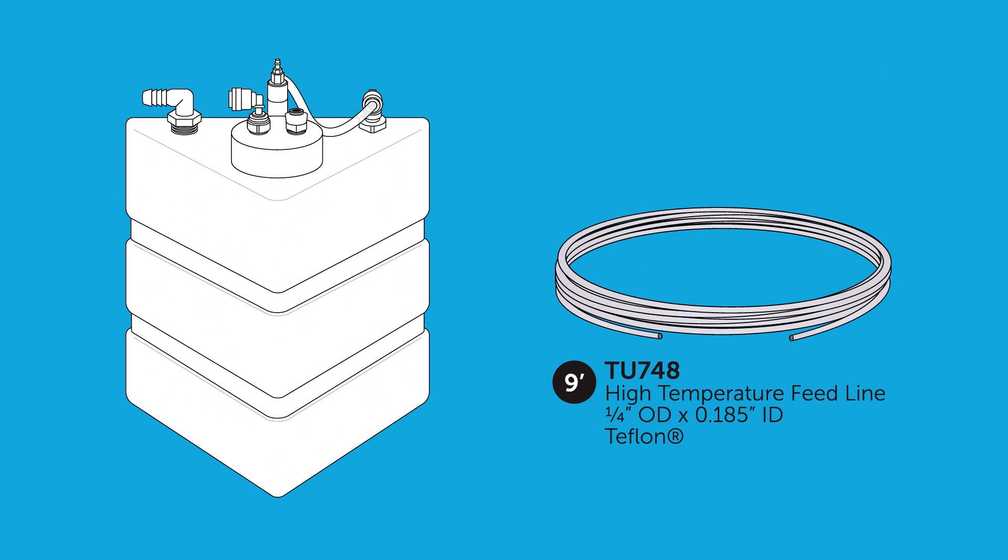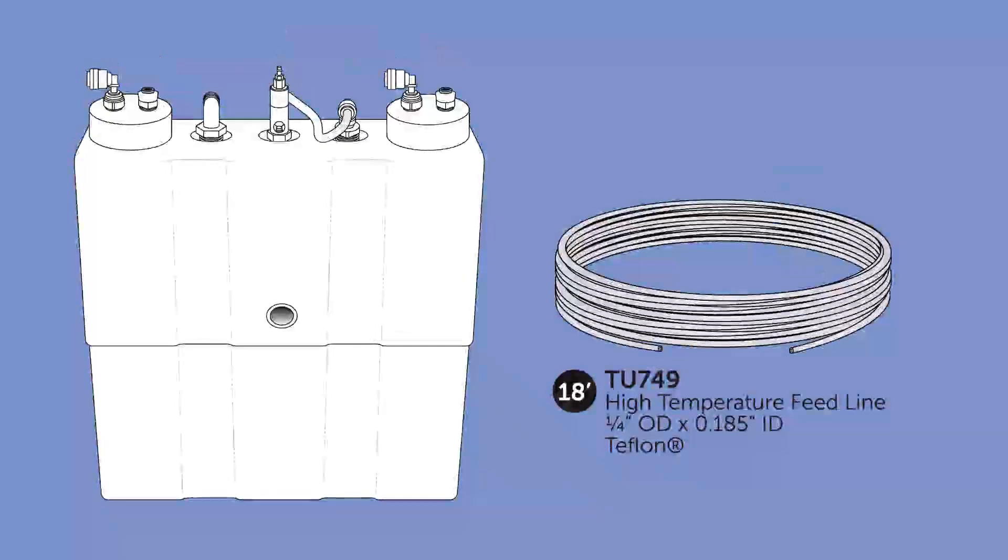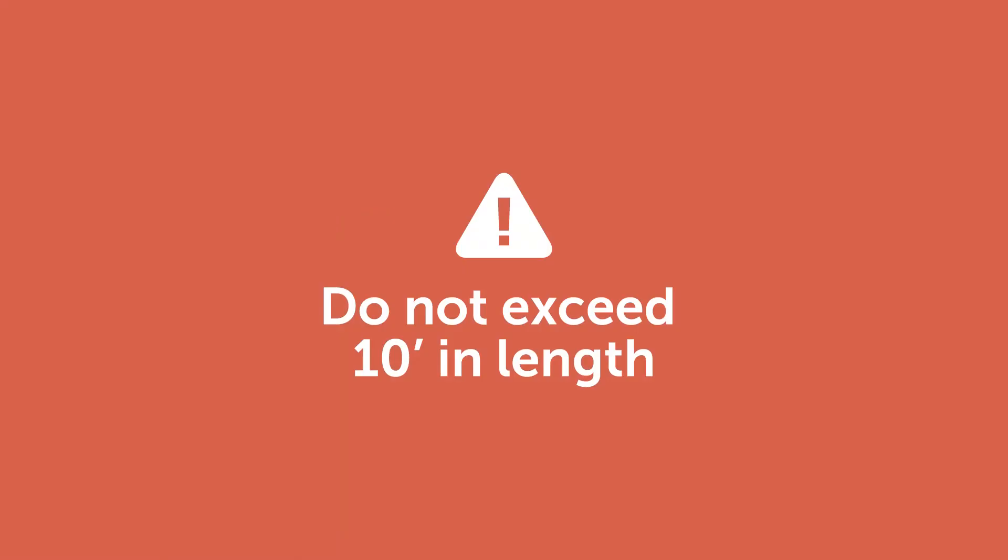A 9-foot length of the high temperature Teflon tubing is included with each model V7501 for a single autoclave, and an 18-foot length is included with each V7502 system. It's important not to exceed 10 feet in length for any individual section of tubing between a sterilizer and the VistaCool.